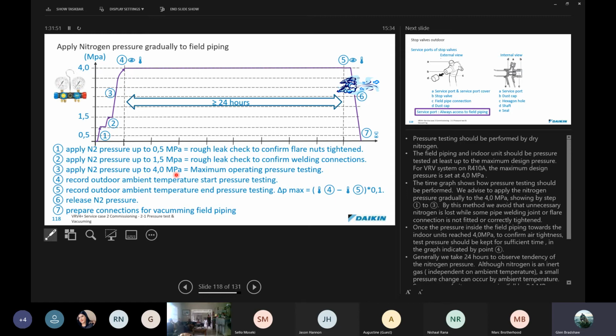What I do recommend is that you take your gauge, and I always put a piece of masking tape over mine, and then I write on that masking tape the starting pressure and ambient temperature. So when I come back, it's there. Take a photograph of it; most guys have camera phones today. Record your outdoor ambient temperature and your end pressure testing. You can use this formula here to work out the delta P max. Then release the nitrogen. Prepare the connections for the vacuuming field piping. This is obviously after you've installed all the components.